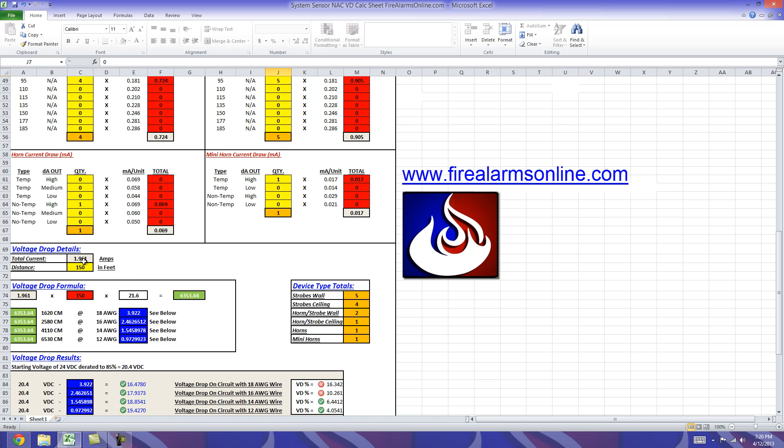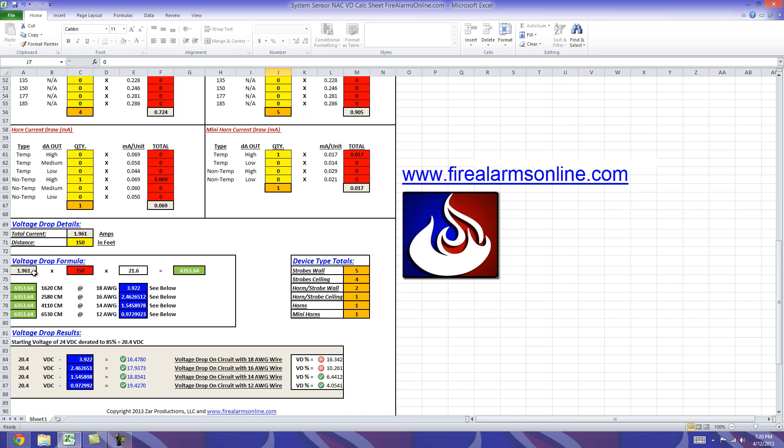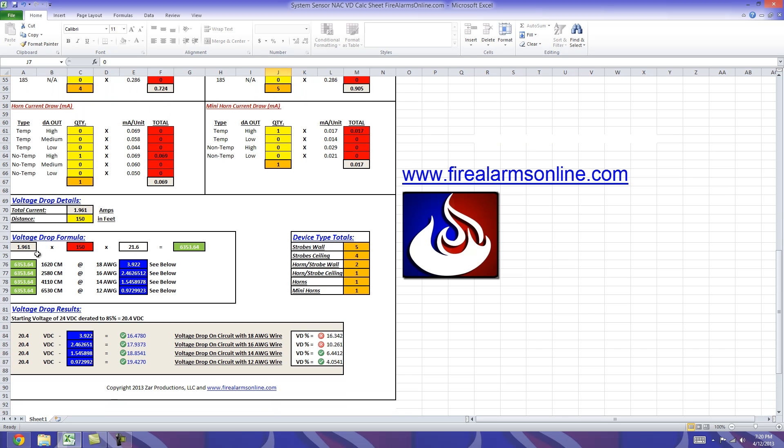And now that we've done that our voltage drop formula has the numbers it needs to start calculating everything. You'll notice here the total current carried down again to the voltage drop formula as well as the footage for the distance and then we have our factor of 21.6. We multiply these three together and we get 6,353.64 and that number carries down to the four sections here or the four cells.